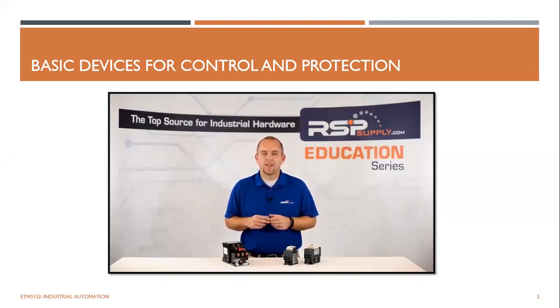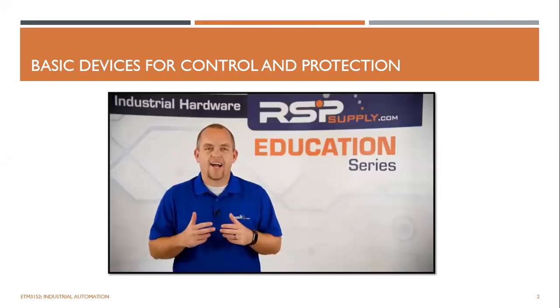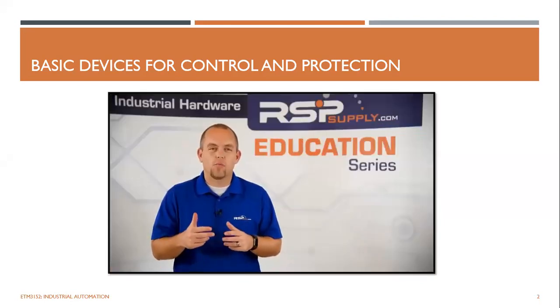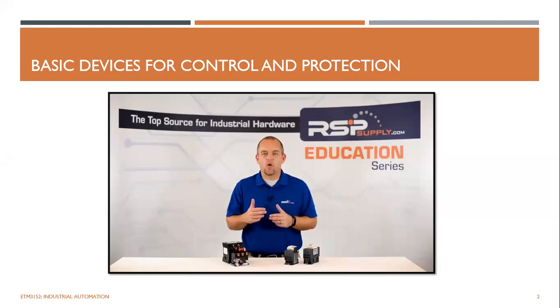The first is a contactor. The second is an overload. And they are commonly used with some sort of circuit protection. So contactors actually provide the current to our motor. Their job is to establish and interrupt power in an electrical circuit. Overload protection protects the motor from drawing too much current over a longer period of time, which can cause the motor to overheat and burn up.